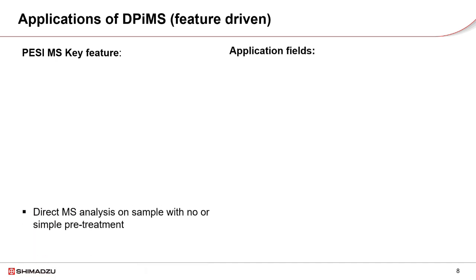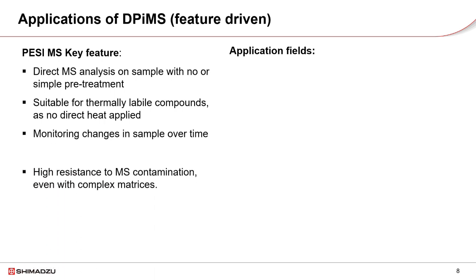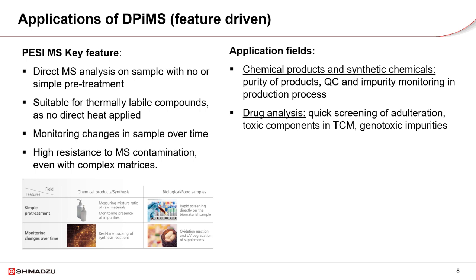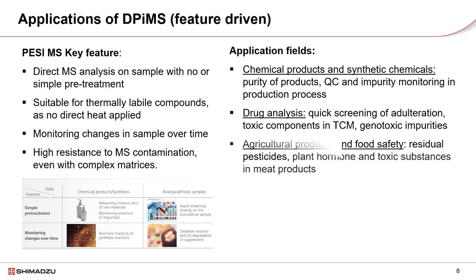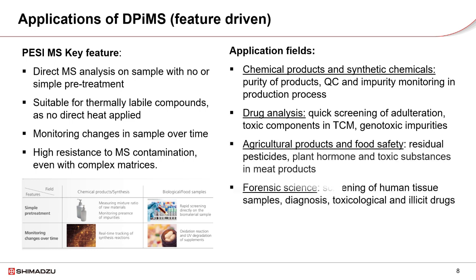Applications of DPI-MS are driven by its key features. Since no or simple sample pre-treatment is required, analysis is fast and easy, suitable for monitoring composition changes over time. With no heating during ionization, DPI-MS is suitable for thermally labile compounds. Sampling at the picoliter level minimizes contamination, making DPI-MS a robust solution for high-complexity matrices such as blood, urine, or food samples.